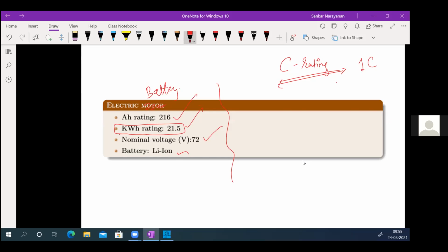Suppose if you have 21.5 kilowatt hour, but your power rating is, say, 43 kilowatt. Your power rating is 43 kilowatt, but your energy rating is 21.5 kilowatt hour. Then you can say it is a 2C rating. Your power is higher, your kilowatt hour is less. So you can actually put your kilowatt divided by your kilowatt hour, it will give you the C rating. So it says that your power rating is more, but your energy rating is less. So your battery is capable of handling more power.